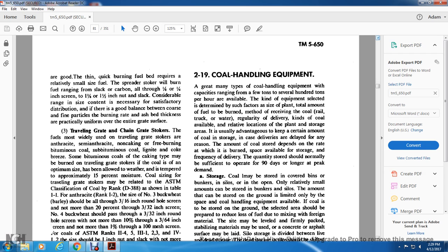The traveling grate or chain grate stoker is widely used. The traveling grate stoker will burn anthracitic, non-coking, free-burning bituminous coal, subbituminous coal, lignite, and coke breeze. Bituminous coal of the coking type may be burned on the traveling grate stoker with the coal at an optimum size, allowing for weather and temperature, with approximately 15% moisture in the coal.